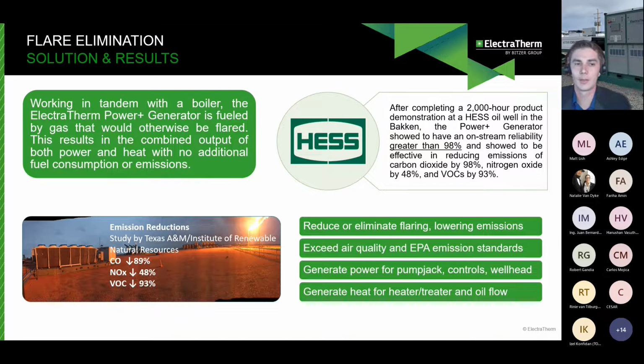So we did do a study in the Bakken Shale here, working in tandem with a boiler, and it was a Texas A&M study, from their Institute of Renewable Natural Resources. Just by removing the enclosed flare and adding a boiler system, it reduced carbon monoxide emissions by 89%, NOx by 48%, and VOCs by 93%. So it does allow us to not only reduce and eliminate flaring, but exceed air quality standards, and then generate additional power for site loads, whether it's pump jack controls, wellheads, or as I mentioned earlier, heat trace, or switching to pneumatic valving. So that was actually a HESS study there. We will be doing another presentation or webinar later in the year on flare elimination as well, so be on the lookout for that.